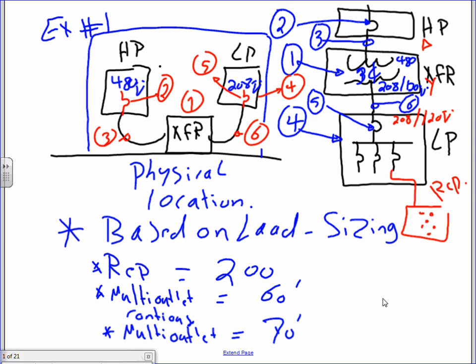Cool. The 480/277, Karen, will be burning all your mechanical equipment, the air handling unit, the chillers, the cooling towers, the pumps, and what not. And your lights through a lighting panel, all your lights, we burn them at 277. And then we need a special panel called a receptacle panel so we can burn our 120 receptacles. Now, how are you going to get 120/208 from 480/277? You need a transformer. What you're looking at is very typical in the electrical industry.